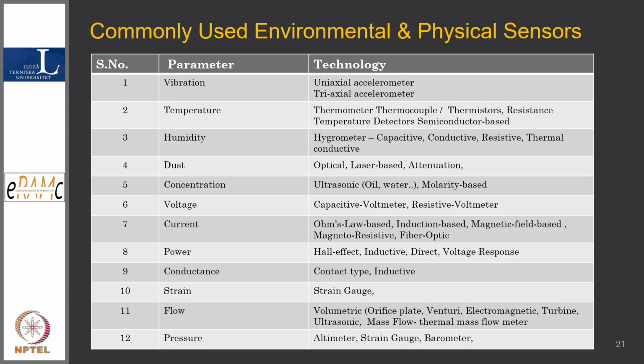Now, for a given parameter or application, there are some sensors. For vibration, you have uniaxial accelerometers, because vibration can be monitored on one axis, or X, Y, Z three axis - triaxial and uniaxial. If we use only a uniaxial accelerometer oriented to X, the Y and Z dimensions will be missing. So for complete information, we should use a triaxial sensor, getting information from X, Y and Z axis.